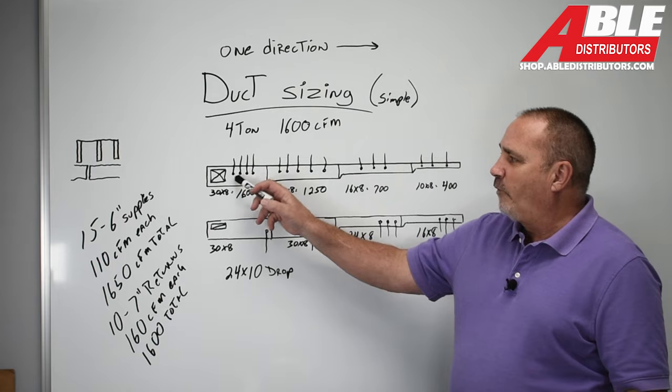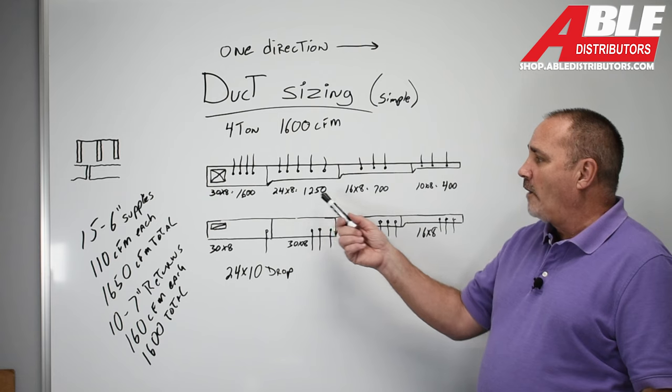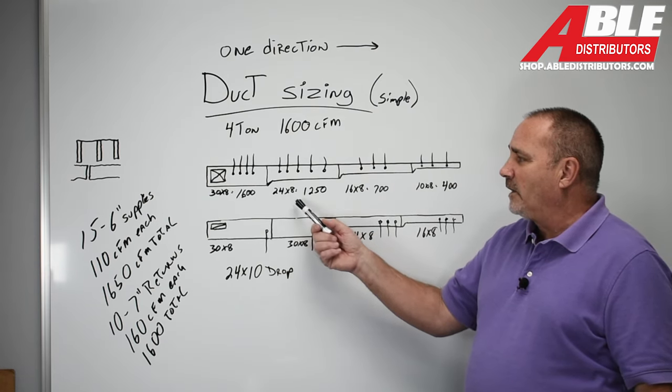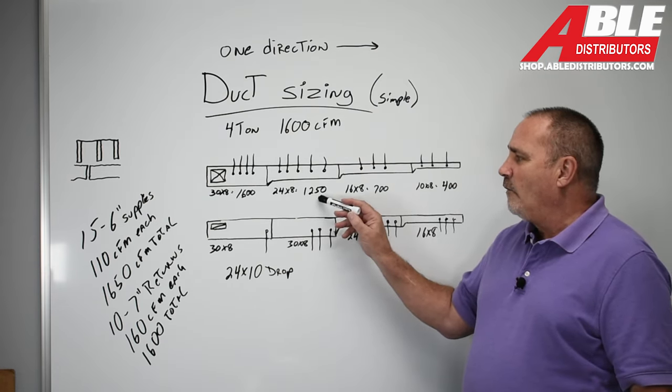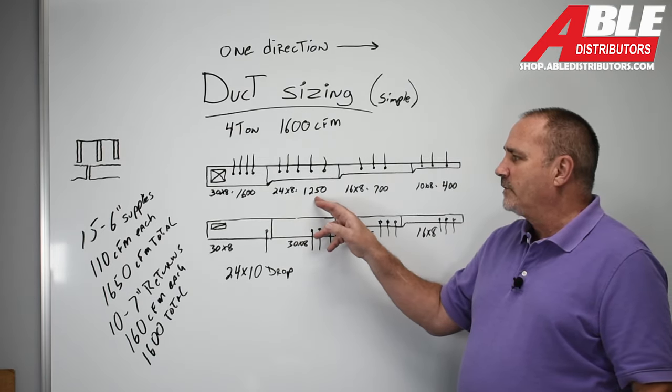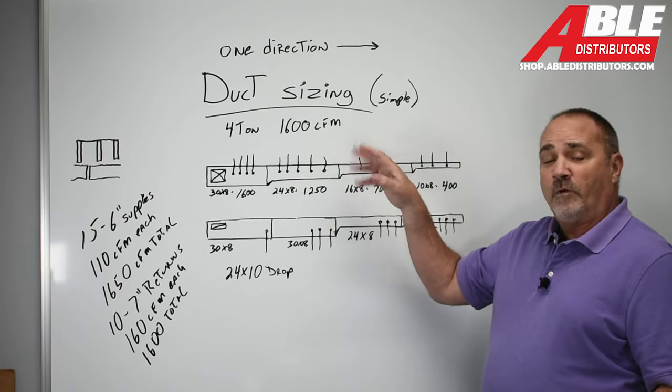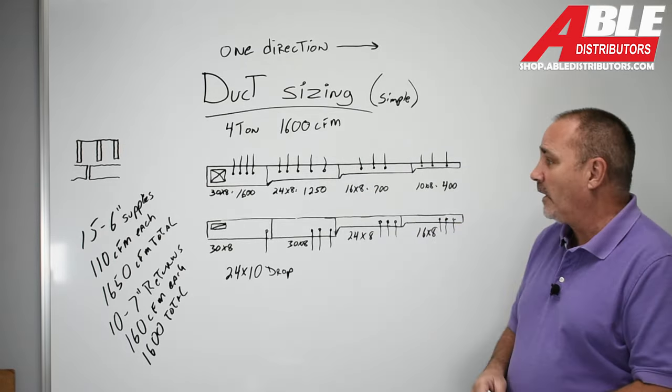So I took four off that first piece. That's roughly 440 CFM off. So the next piece I dropped down to 24 by 8. It's a little oversized because we took 440 off of that. So we're a little oversized, but 24 by 8 is good for 1,250. We took five more supplies off of that. That's 550 CFM.